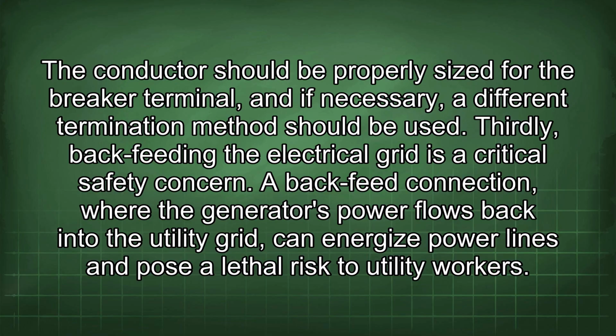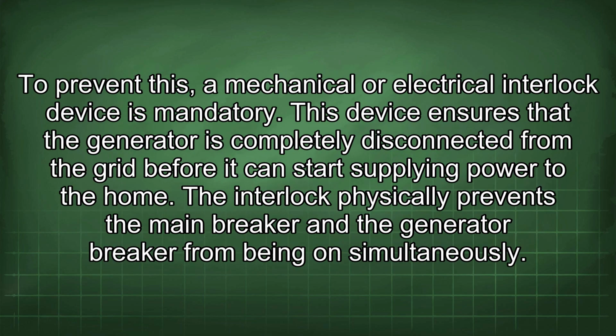Thirdly, backfeeding the electrical grid is a critical safety concern. A backfeed connection, where the generator's power flows back into the utility grid, can energize power lines and pose a lethal risk to utility workers. To prevent this, a mechanical or electrical interlock device is mandatory. This device ensures that the generator is completely disconnected from the grid before it can start supplying power to the home. The interlock physically prevents the main breaker and the generator breaker from being on simultaneously.